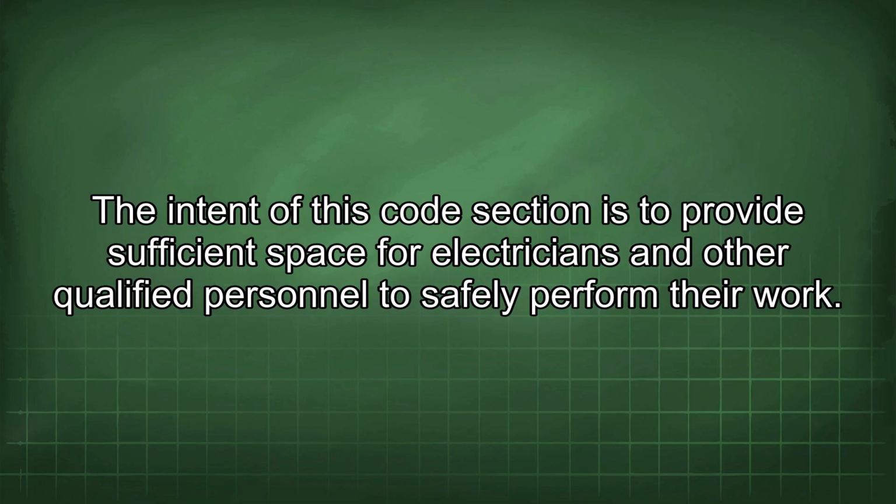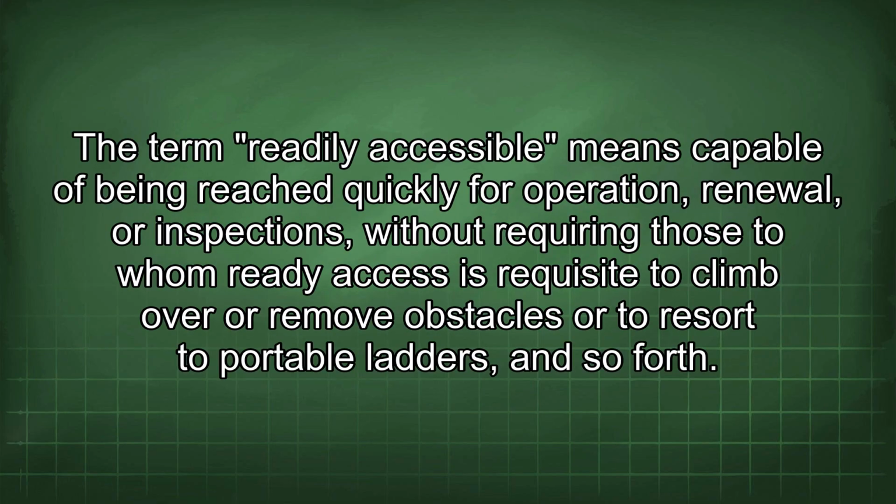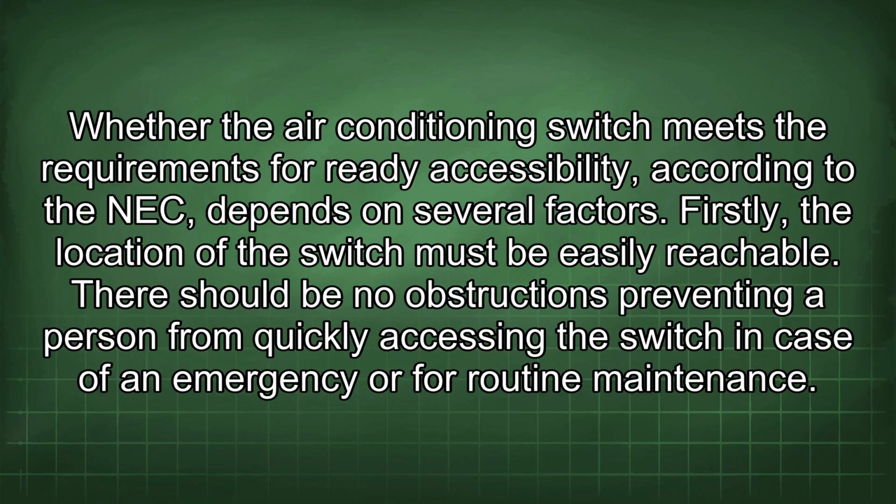perform their work. The term readily accessible means capable of being reached quickly for operation, renewal, or inspections without requiring those to whom ready access is requisite to climb over or remove obstacles or to resort to portable ladders, and so forth. Whether the air conditioning switch meets the requirements for ready accessibility according to the NEC depends on several factors. Firstly, the location of the switch must be easily reachable.